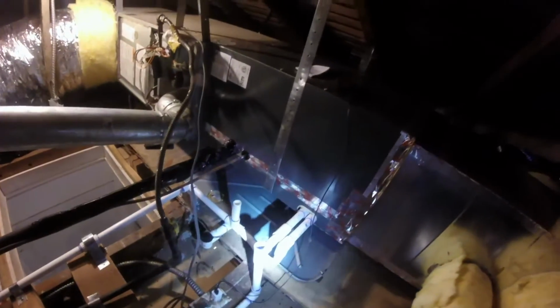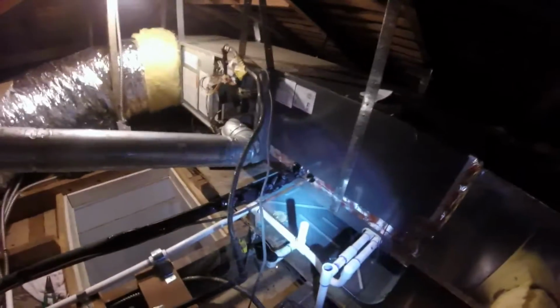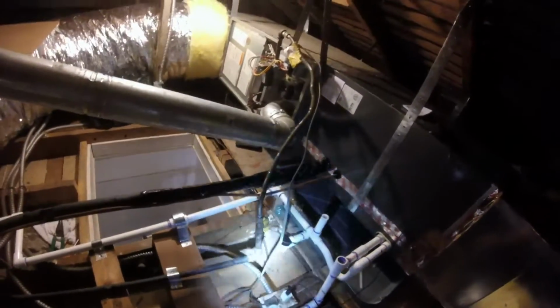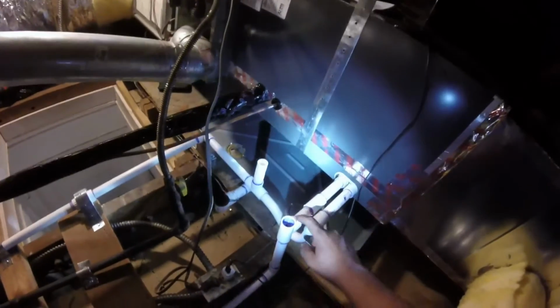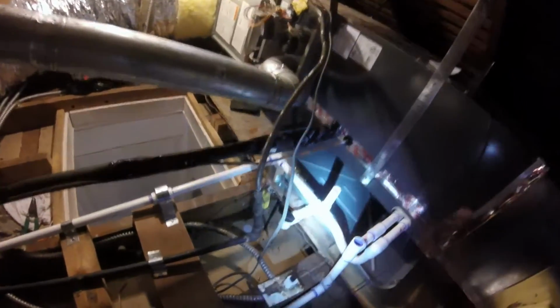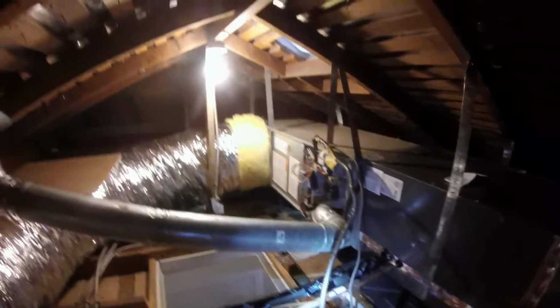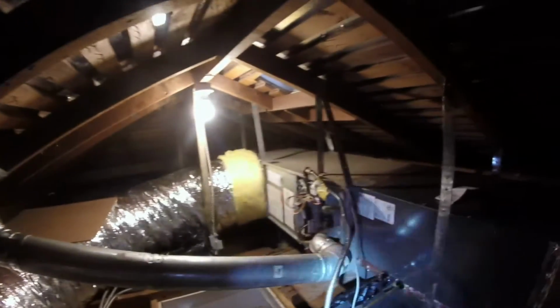But hope you like what you saw. Drain pan can't move. It's only there to trip the float. I know some guys like to run their secondary to the pan, but then they can't use the AC. I like this configuration a lot better. And we're out of here.